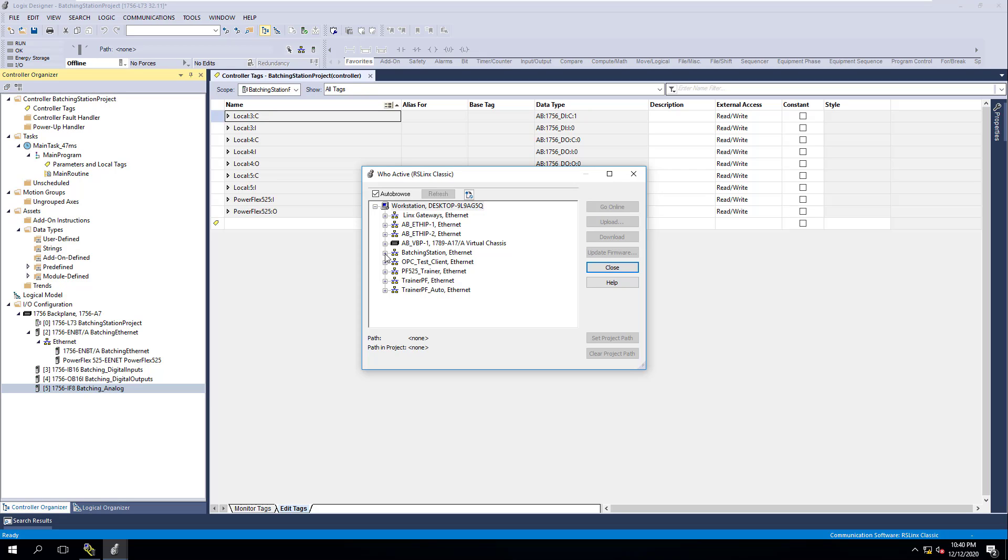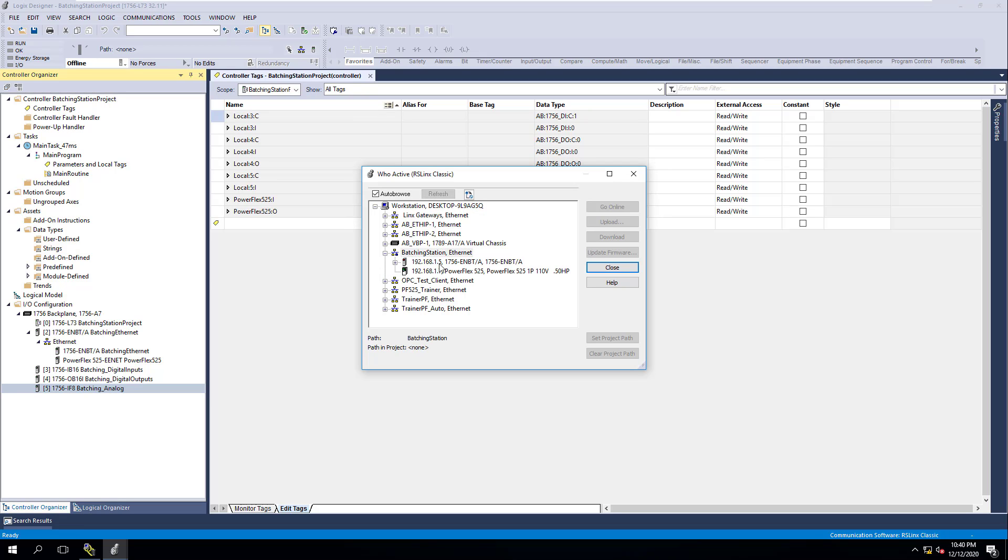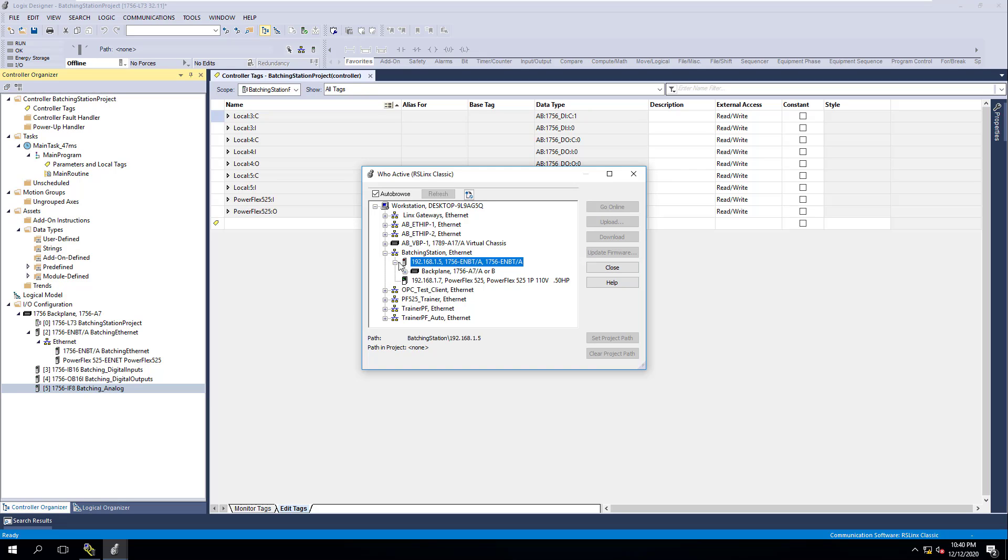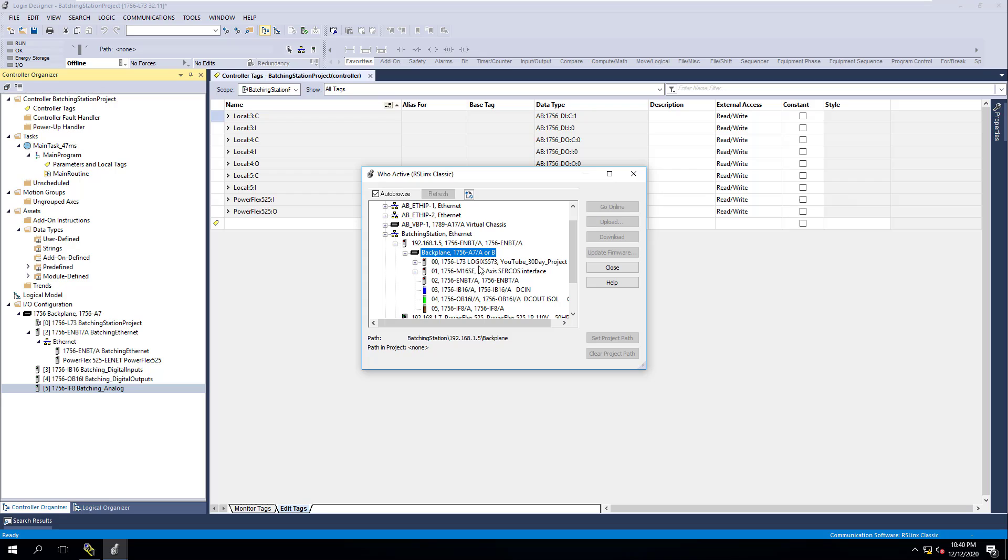You need to select exactly where you're doing this to. Make sure you're specific. In our case, this is why we made our driver. Batching Station Ethernet is where we're communicating right now. We're coming back to our Ethernet card, communicating back to our processor rack. This opens up the backplane of the actual 1756 communication, and then now we're going to select slot zero, which is our processor, the 1756-L73.